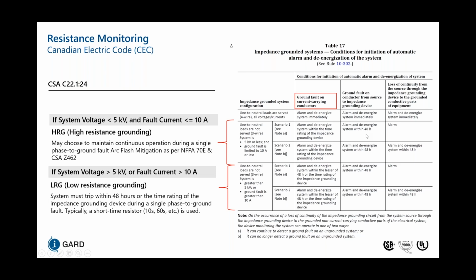So going back to Table 17, the requirements are that we need to alarm and de-energize within 48 hours when there's a short circuit condition. And when there's an open circuit condition, we either alarm if we can still detect a ground fault in an ungrounded system, or alarm and de-energize the system within 48 hours. So our current relay, the Sigma 3C, has this built-in 48-hour delay so that you don't have to utilize an interposing time delay relay in conjunction with our relay to accommodate this additional 48 hours that the code is allowing for.